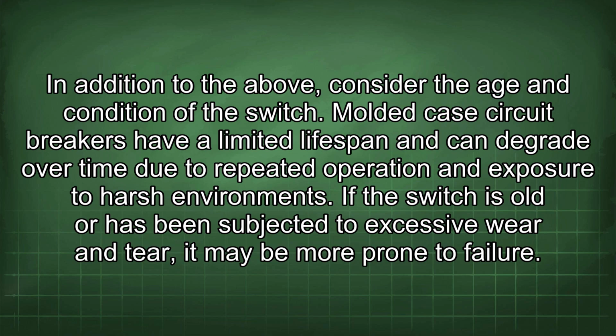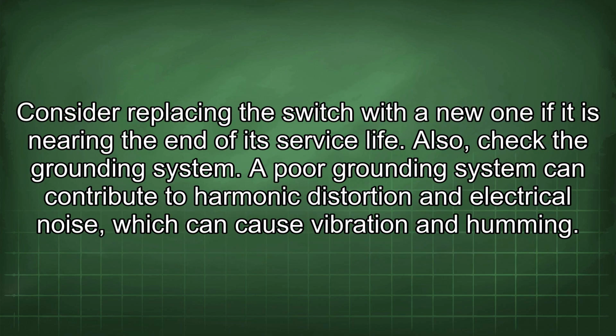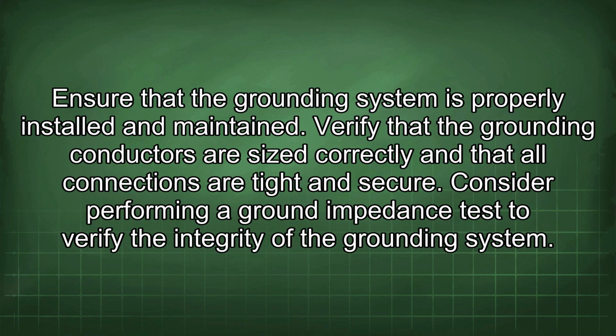If the switch is old or has been subjected to excessive wear and tear, it may be more prone to failure. Consider replacing the switch with a new one if it is nearing the end of its service life. Also, check the grounding system. A poor grounding system can contribute to harmonic distortion and electrical noise, which can cause vibration and humming. Ensure that the grounding system is properly installed and maintained. Verify that the grounding conductors are sized correctly and that all connections are tight and secure. Consider performing a ground impedance test to verify the integrity of the grounding system.